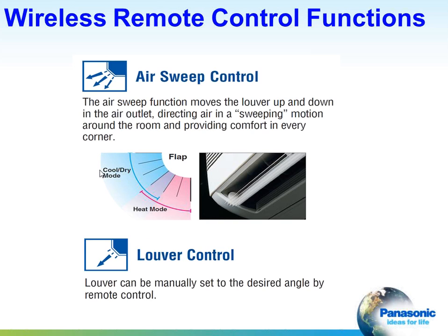The louvers on the high wall units and the ceiling cassettes can be controlled. There's an automatic air sweep control, and if you look at the top diagram, in the cool mode, the flap or the louver will circulate the cool air so it's thrown across the room so it can fall into the occupied space. So we bring the air out at a higher elevation to cover the room better. In the heating mode, we want to get that heat down to the floor where people are, and so the louver operates in that lower setting right there. Or you can fix the louver in a fixed position.